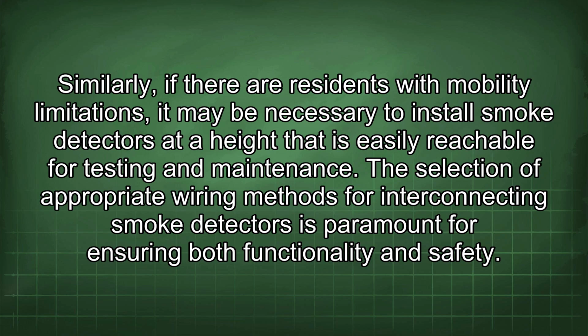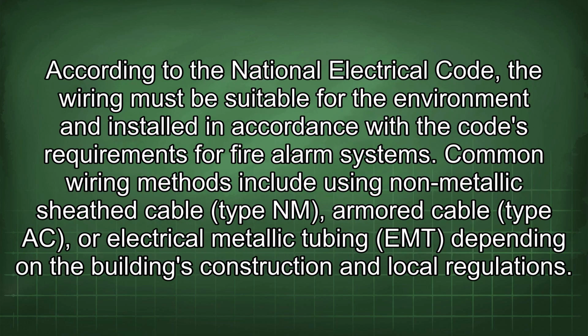The selection of appropriate wiring methods for interconnecting smoke detectors is paramount for ensuring both functionality and safety. According to the National Electrical Code, the wiring must be suitable for the environment and installed in accordance with the code's requirements for fire alarm systems. Common wiring methods include using non-metallic sheathed cable type NM, armored cable type AC, or electrical metallic tubing EMT, depending on the building's construction and local regulations.